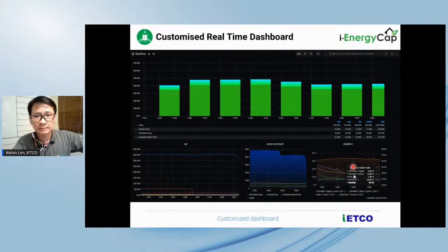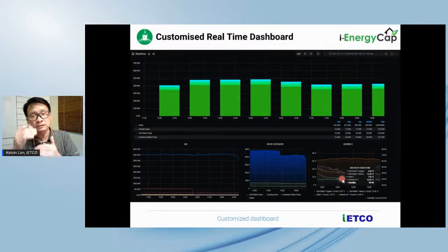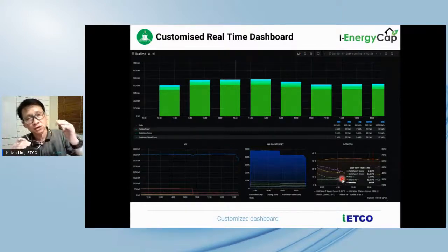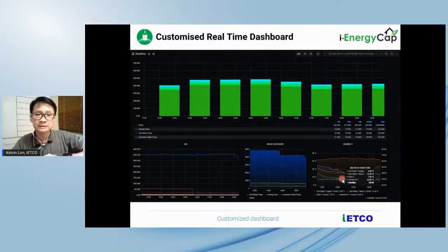For this example, we are monitoring and tracking the delta T of the chill water, maintaining the delta T as specified in design, with no fluctuation. This tells us the pumps are running according to design and being controlled properly. But without real-time data, you would not be able to see such operations.